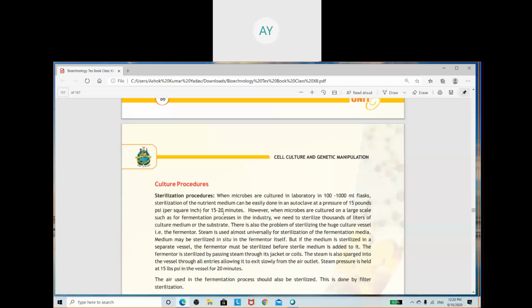That duration will vary as per the volume which we are going to autoclave. So if we are increasing the volume from 100 to 200, 300, 400, 500, 600, 1000 ml, then we have to increase the duration of time also.